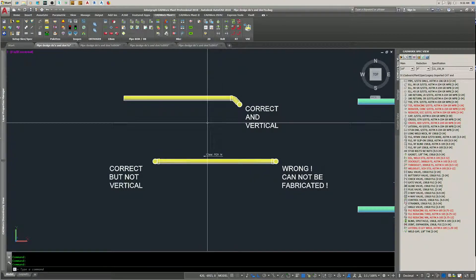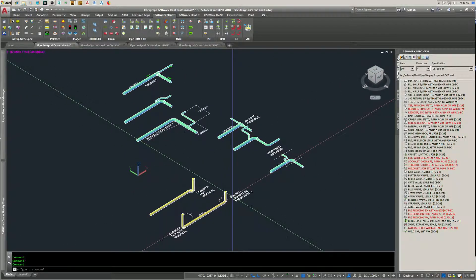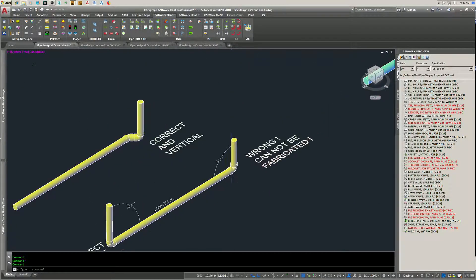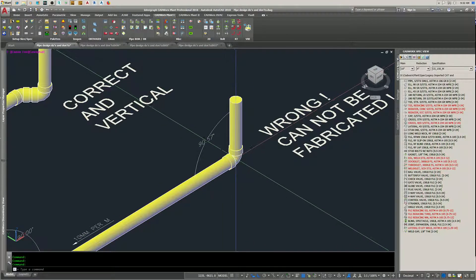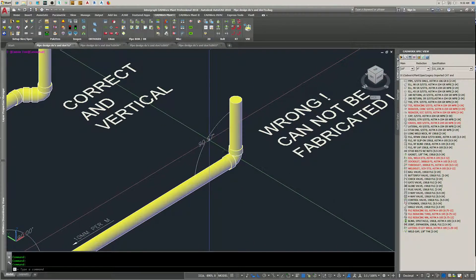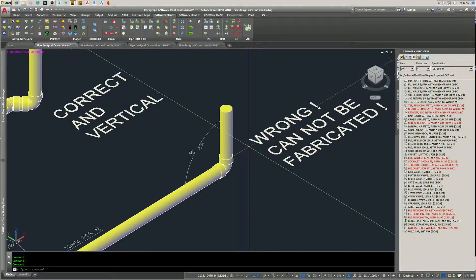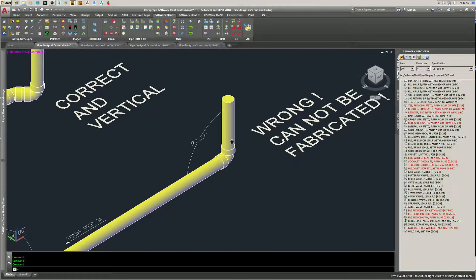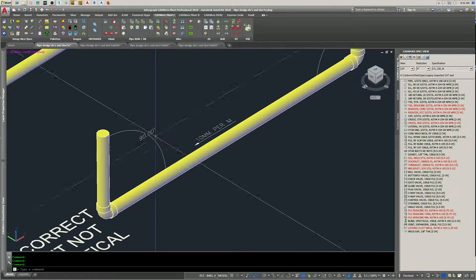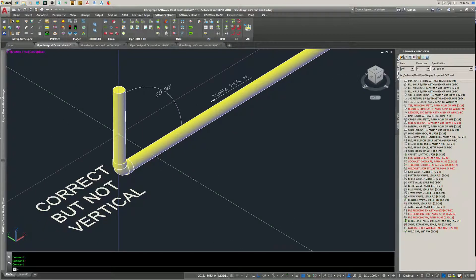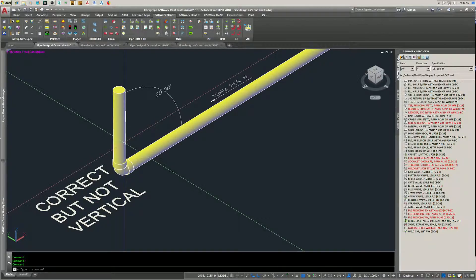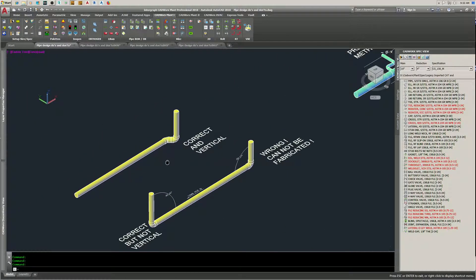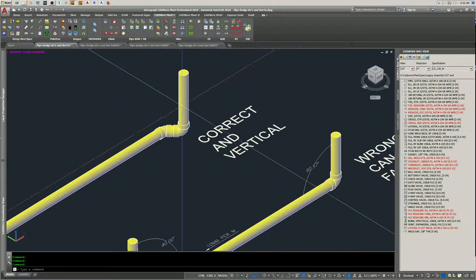Now sloped pipe - let's get over here in an ISO view. This is a 90 degree socket, this angle is impossible. This cannot be fabricated. It won't go in that way, it's going to go in this way, 90 degrees. And this will not be vertical. If you want this vertical, you have to add another fitting so this can be rotated into the vertical.